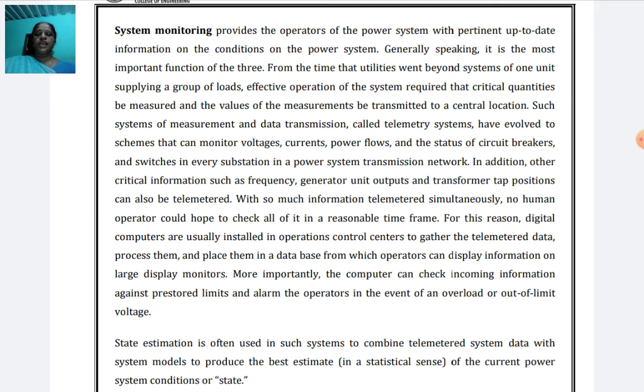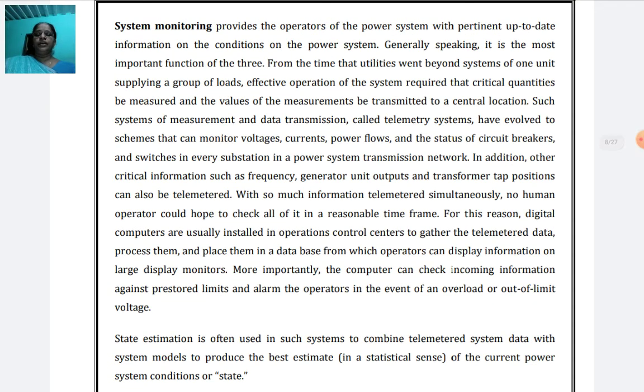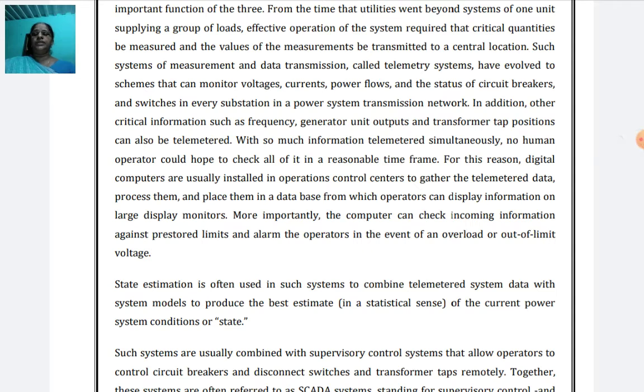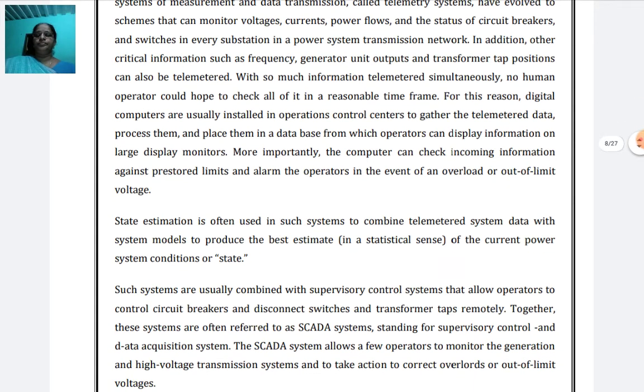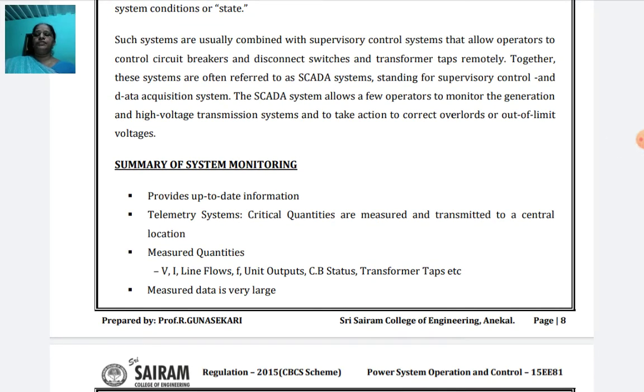In this case, we are using State estimation, and we can collect the telemetry data from remote areas by using digital communication. Telemetry data means voltage, real power, reactive power, frequency, generator unit output, transformer tap positions; all are telemetered data, which is telemetered into the database. A system of measurement and data transmission is called the telemetry system, which has evolved to schemes that can monitor different telemetered data. Then the summary of system monitoring: what it provides is up to date information to the system operator.